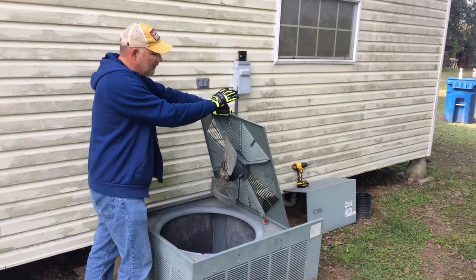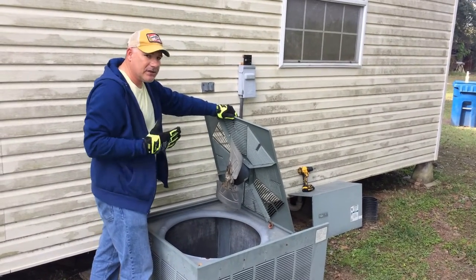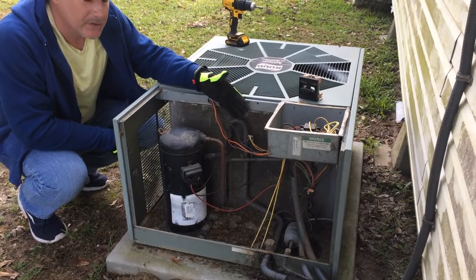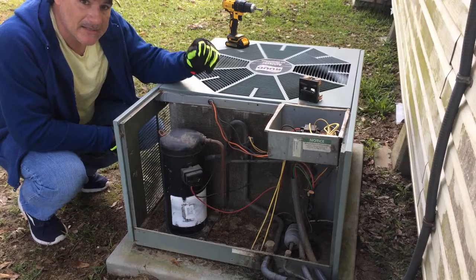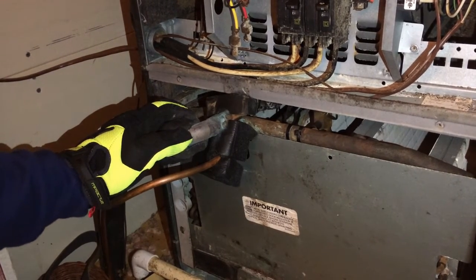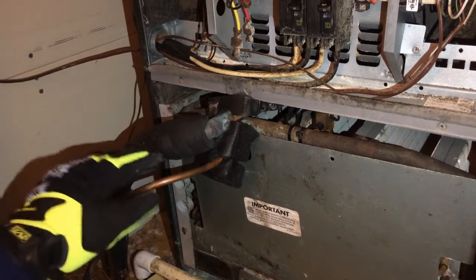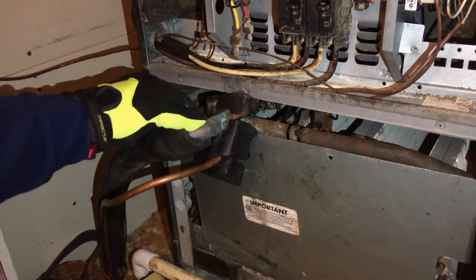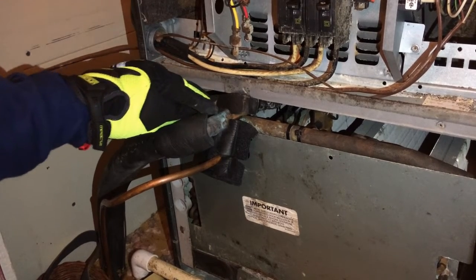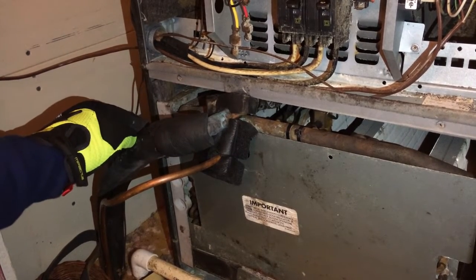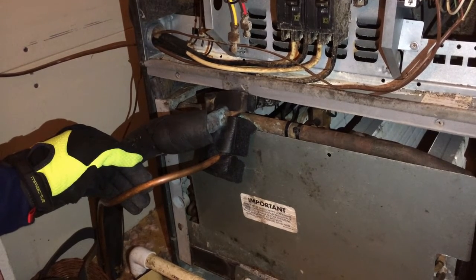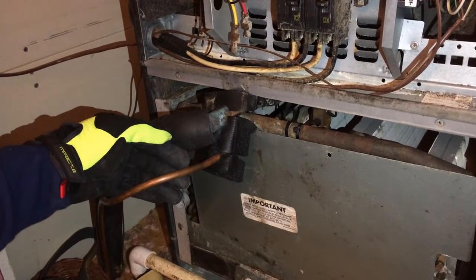The heat you feel coming off of the unit when it's running was in your home just a few minutes prior. But where does the refrigerant come from? Let's go inside and take a look. Inside the house we find the air handling unit, and again we see the small copper line and the large copper line. This large copper line is leaving the evaporator coil and making its way to the outside compressor. The small refrigerant line is actually refrigerant entering the air handling unit.